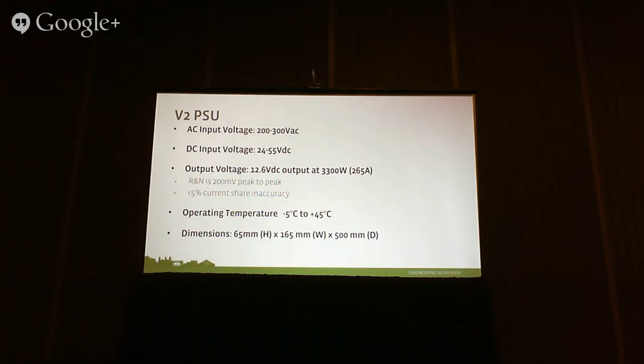The battery charger circuit inside the power supply is 270 watts. It takes the input from the bulk voltage and steps it down to a precise 52.5 volts DC plus or minus 0.2% output. The maximum charging current for the battery is 5 amps.